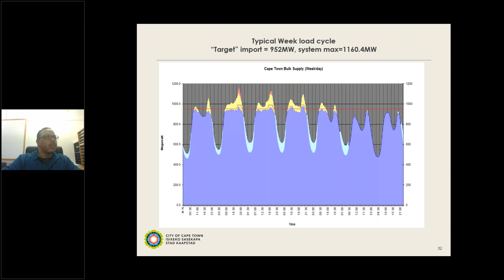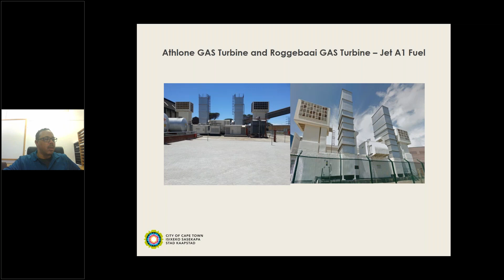Here's an example: on the left is Athlone gas turbine, and on the right is Roggebaai gas turbine, situated just opposite the CTICC. Athlone is the older Olympus machine, running about 35 to 36 megawatts, while Roggebaai is newer and in better shape, sometimes reaching 38 to 39 megawatts as required. Both run on jet A1 fuel and are very expensive to operate, consuming about 15,000 to 16,000 liters per hour. We very rarely run these units, but they're available when needed, provided they're healthy.